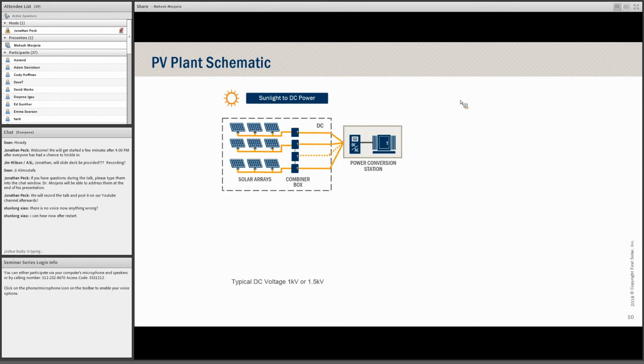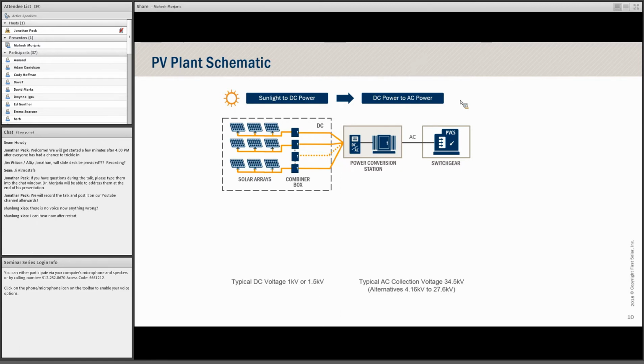Then there's a power conversion station that converts the DC power into AC power and steps it up. Typical AC collection voltage is about 34.5 kV AC. This is also used in wind plants, which is why this voltage level was adopted. Then that power is aggregated further, using switch gears, and fed into a substation that steps it up to anywhere from 69 to 765 kV AC.